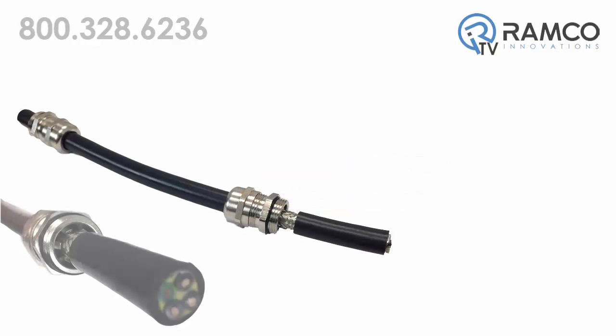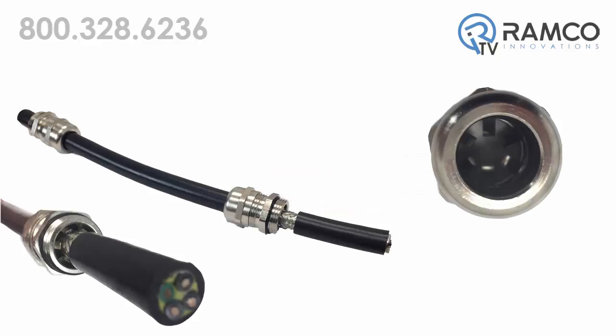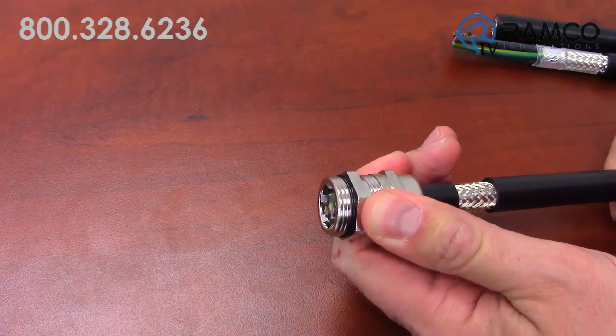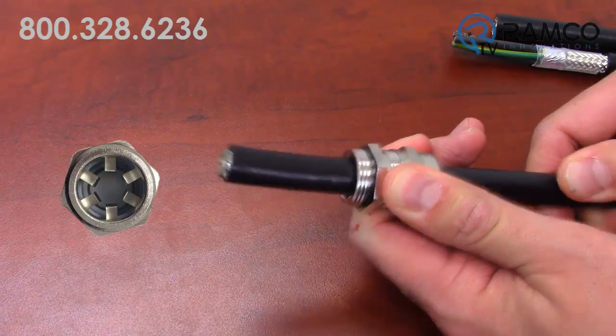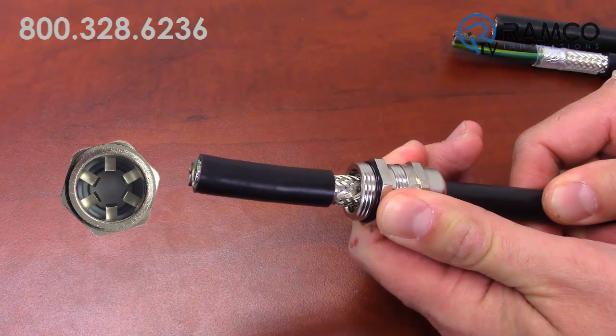Cord grips are also available to connect these cables for proper EMI protection. Cord grips such as these not only provide a strain relief and seal, but these little metal tabs also provide a path to ground for the shield.